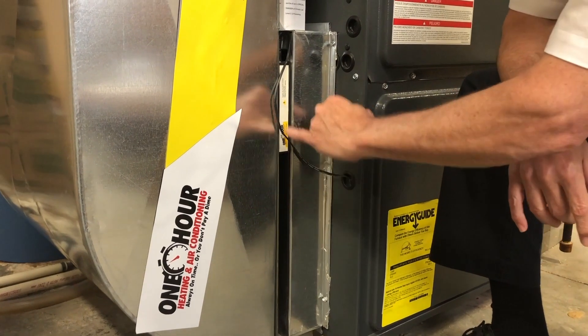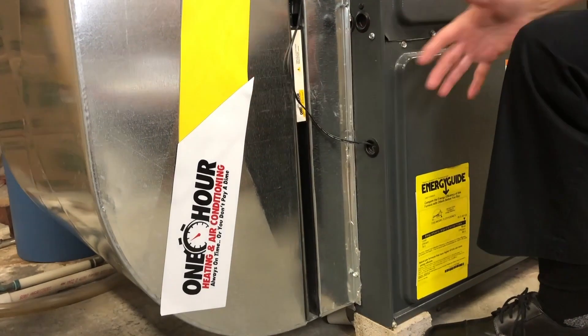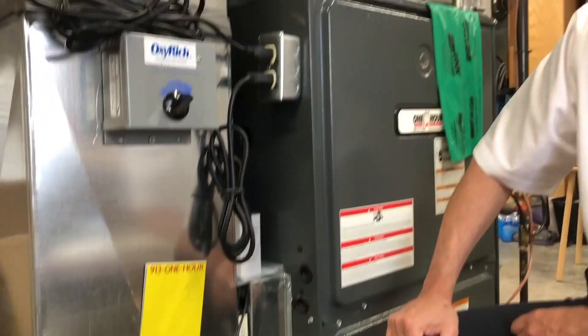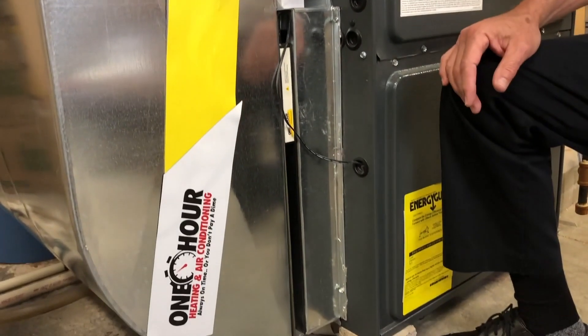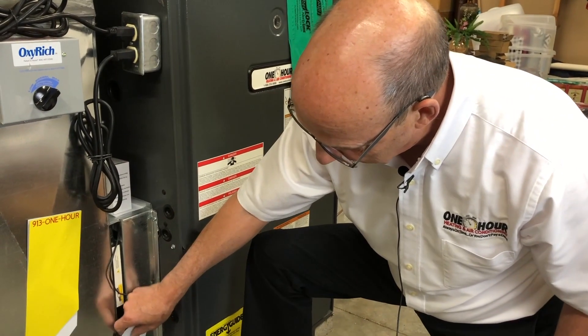A while ago we made a video on the handy furnace filter cover. You can see cracks all around this air filter, and the blower is right here. The amount of air that can leak in is extremely high. We could be in a crawl space, a garage, or somebody's wood shop right now — we're drawing a lot of air from a very contaminated space. I've made my own out of magnetic strip to cover it up.